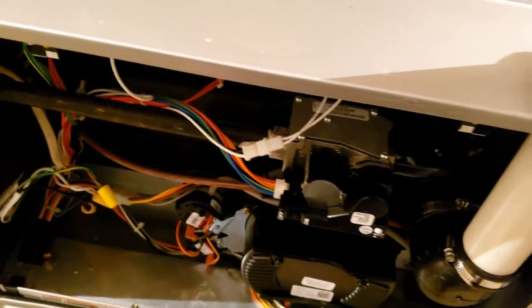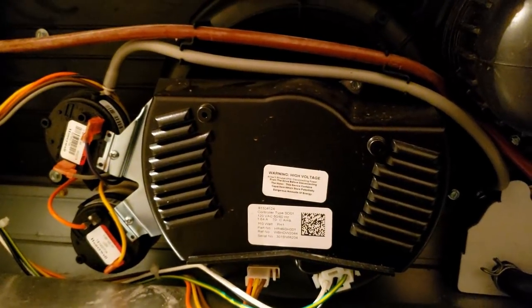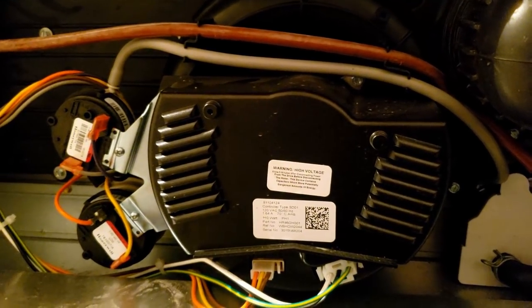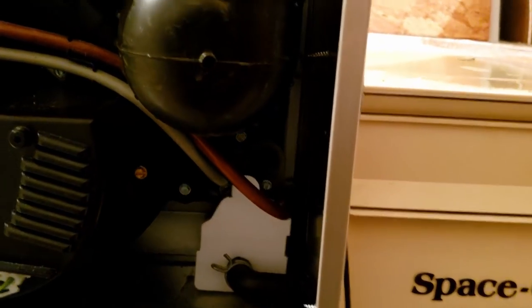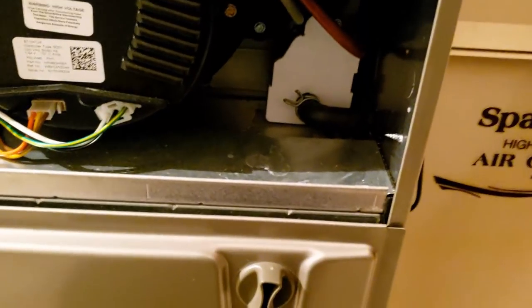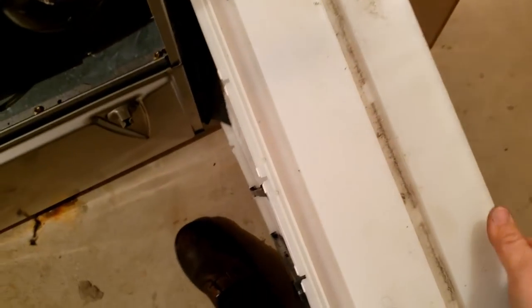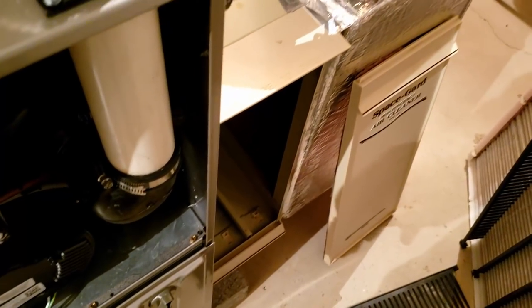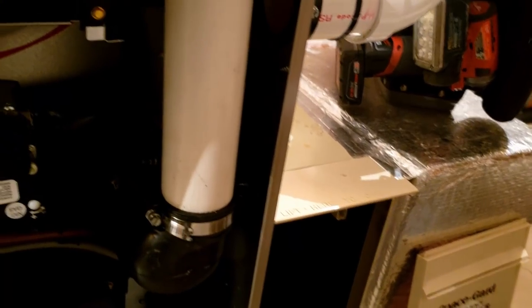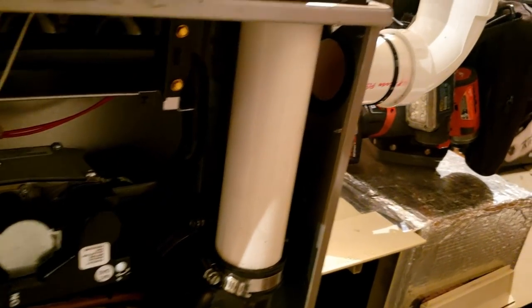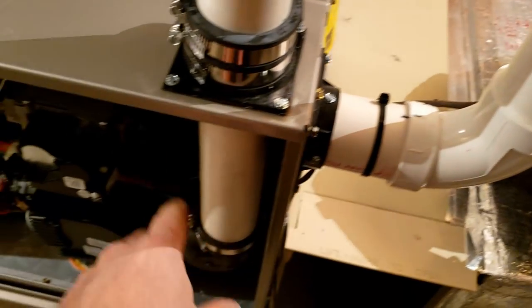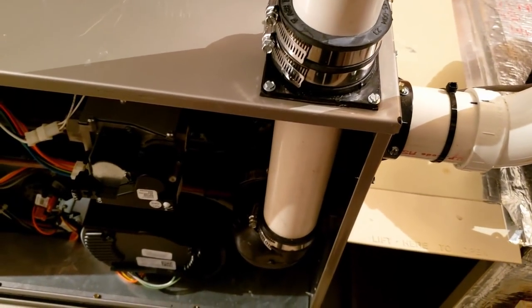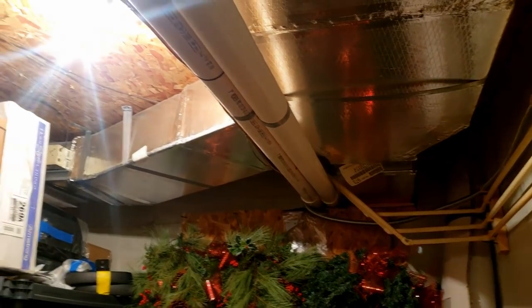So let's see what we got going on. I had one the other day that was kind of crazy, and it ended up being the water was driven into the collector box because they didn't vent the line going from the furnace separately from the air conditioner, and the humidifier was tied in with it and it piled the water up in there. So this looks creative. So there's the drain. That's an interesting one - I actually got that to fit there like that. Alright, so let's see here. At least they brought it in on the side so the cold air doesn't condensate over top the gas valve. They did that perfect. And that goes right out the back side of the house, so we'll go and see if there's any issues there.